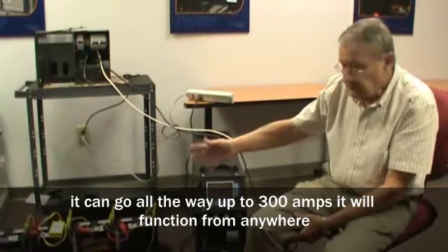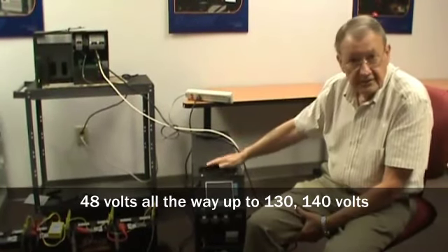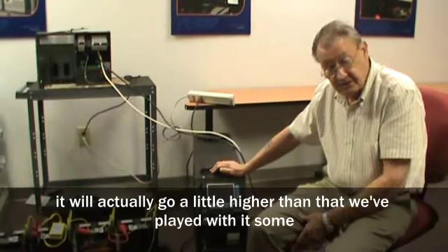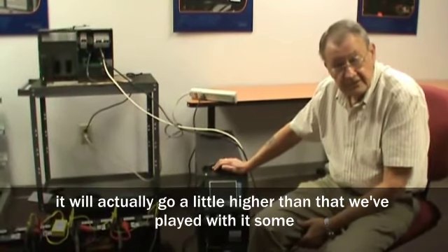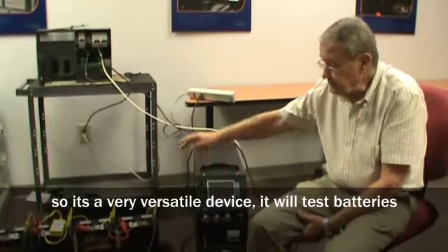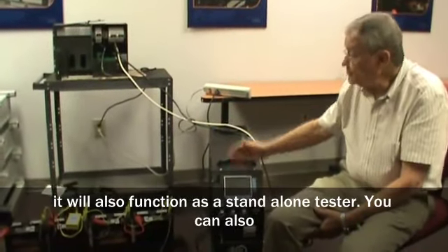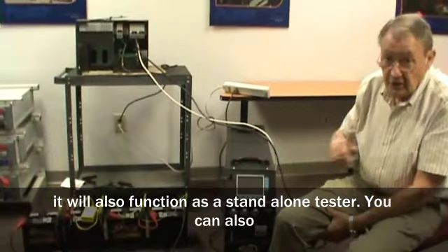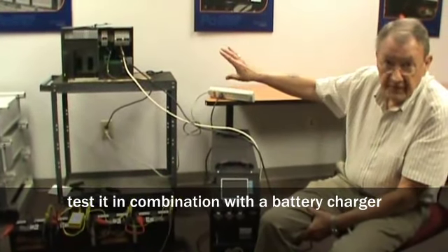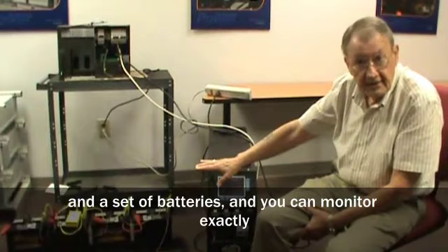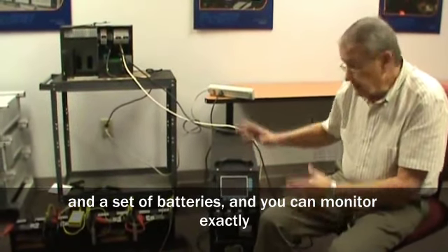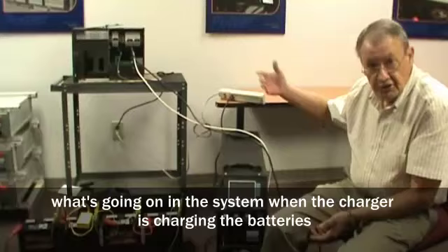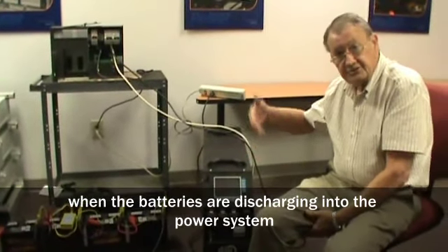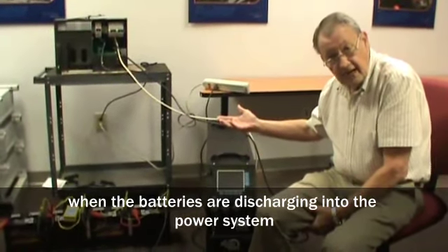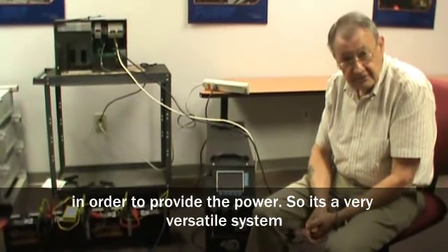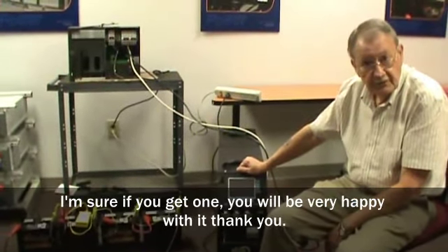It will function anywhere from 48 volts all the way up to like 130, 140 volts. It'll actually go a little higher than that. We've played with it some. So it's a very versatile device. It will test batteries. It will also function as a standalone tester. You could also test it in combination with a battery charger and a set of batteries, and you could monitor exactly what's going on in the system. When the charger is charging the batteries, when the batteries are discharging into the power system in order to provide the power. So it's a very versatile system, and I'm sure if you get one, you'd be very happy.